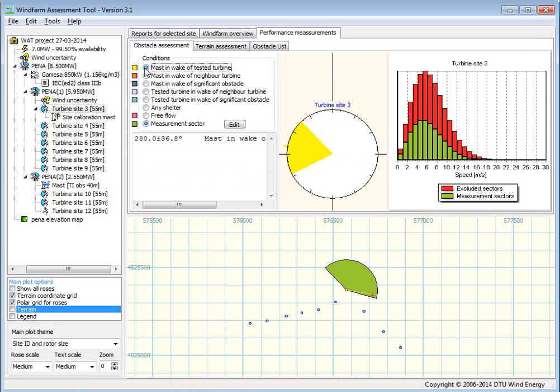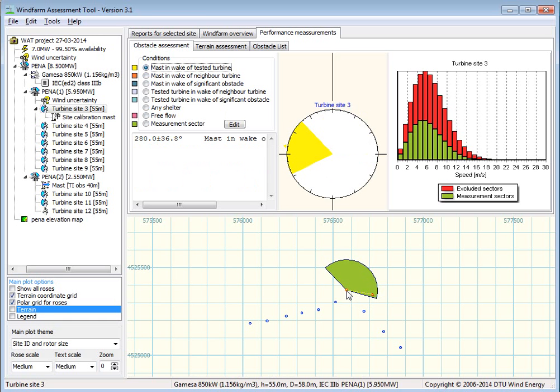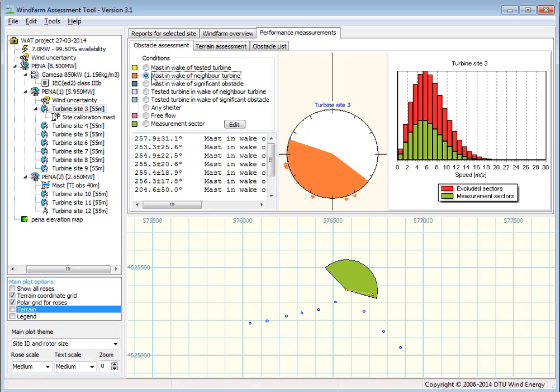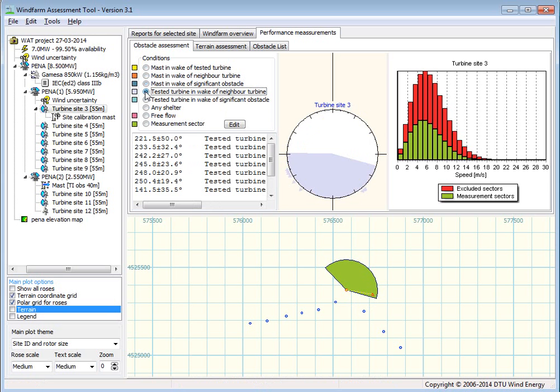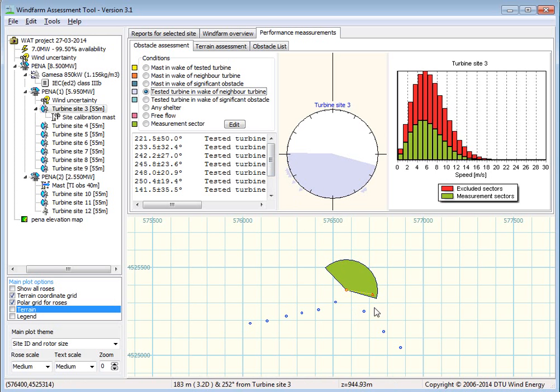There are different kinds of checks we have to make. For instance, the mast should not be in the wake of the tested turbine or other turbines and obstacles. We don't have any obstacles yet, but then the tested turbine should not be in the wake of the other turbines here.